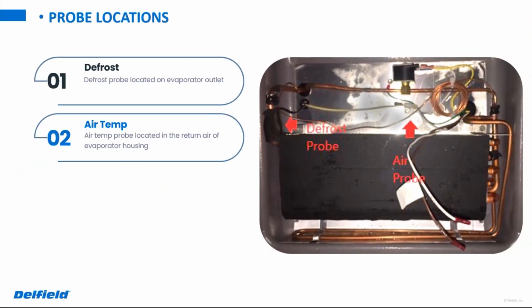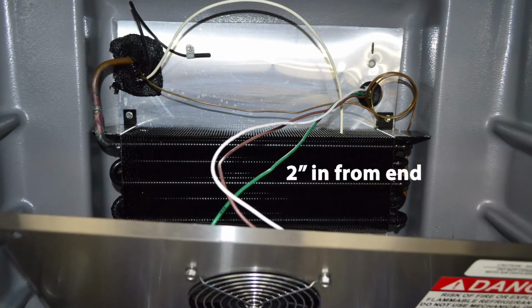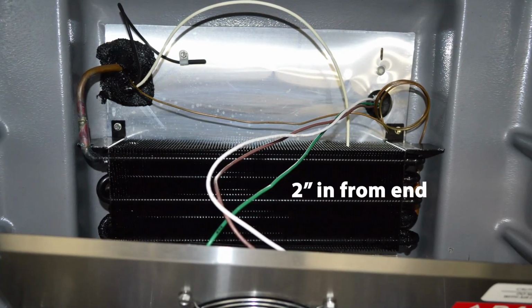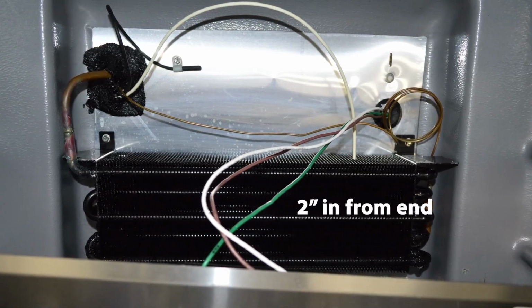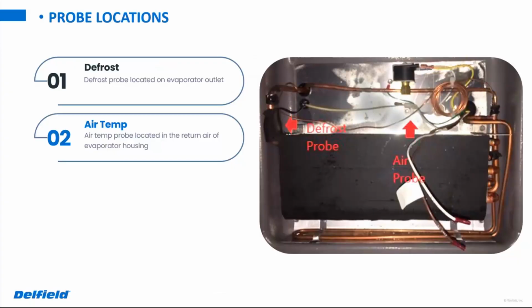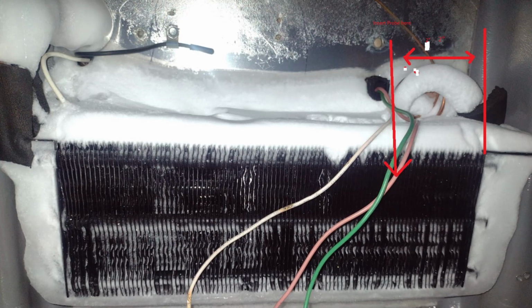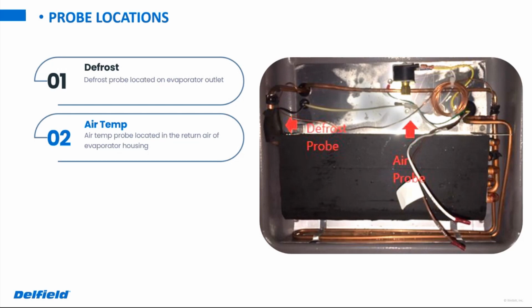However, on some of the coolers, we've had some instances where we've had some frozen up evaporators, and we've been having techs relocate those probes from that suction line to the evaporator coil to help with defrost. So if you happen to see a coil that's maybe frosting up a little bit more than normal and everything else seems to be operating correctly, it might not be a bad idea to relocate that probe from that suction line over to the evaporator coil.